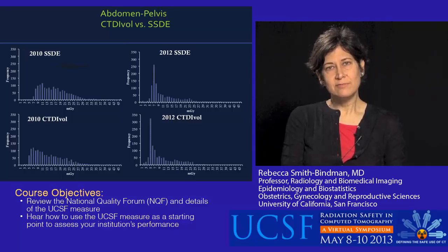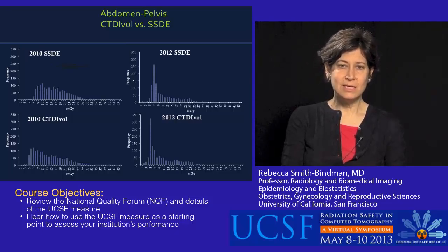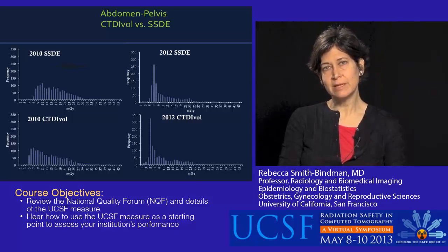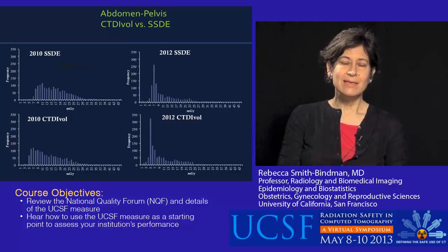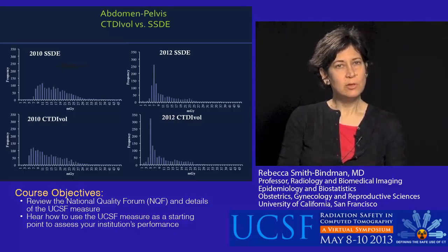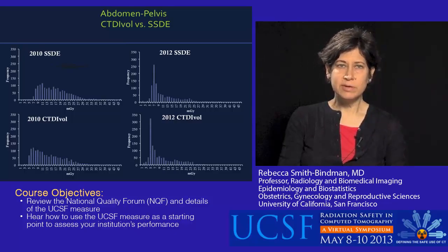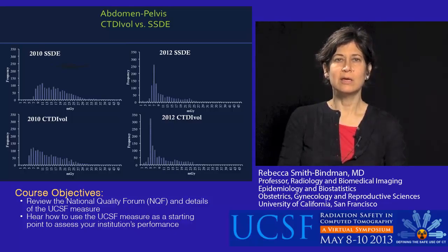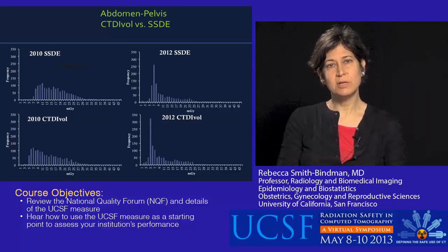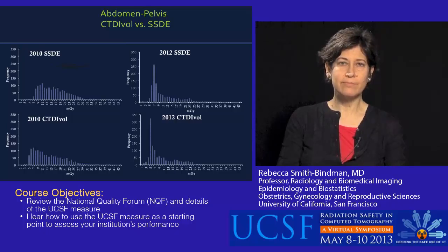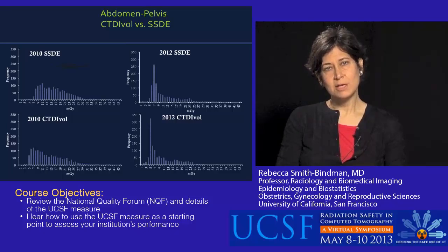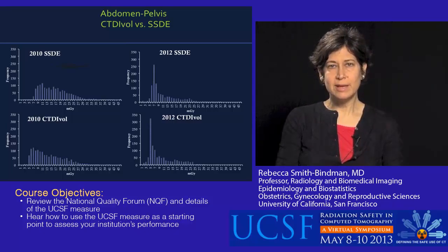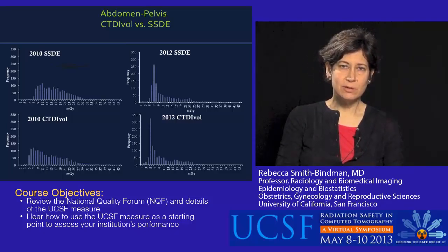We looked at lots of different measures. The measure of SSDE, which I think is an excellent measure, happened not to be specified when I submitted this NQF measure because it had not yet been developed. It is a very nice measure, but for the purpose of looking at how you're doing, in our experience, it doesn't matter how you look. You learn the same things pretty much. So on the left is showing the 2010 SSDE and CTDI, and the right showing the same thing in the latter period, and both give very similar information.